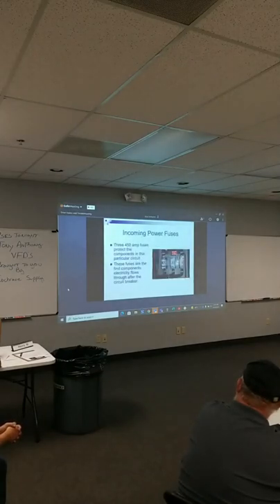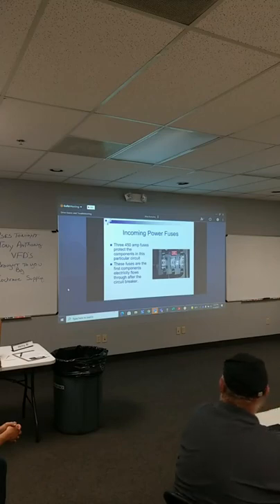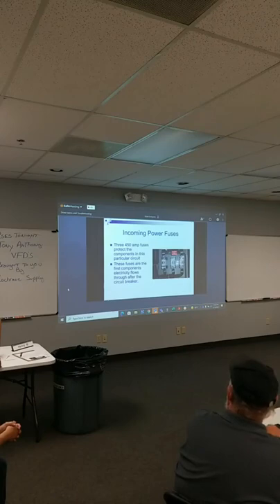Another way to protect the drive is incoming power fuses. Unlike a breaker, these trip and, obviously, you have to replace them. It's a little more time consuming, but they can protect the drive, and so a lot of people still use them. I've actually seen people who like to use a breaker and fuses because they've got to have fuses in the circuit, and they also want a breaker.